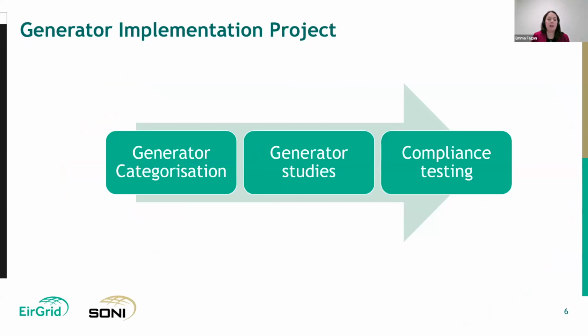One massive part of the project then was after the regulators agreed with the proposed Grid Code change from 0.5 hertz to 1 hertz per second. That was back in 2014, but it was subject to a generator implementation project going ahead, and it really being proven that the higher levels of RoCoF could be implemented by the industry. So this program involved categorization of the generators in terms of their importance to contribute to being able to ride through the higher RoCoF levels.